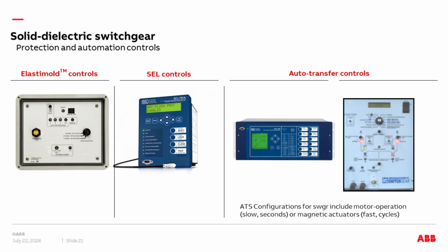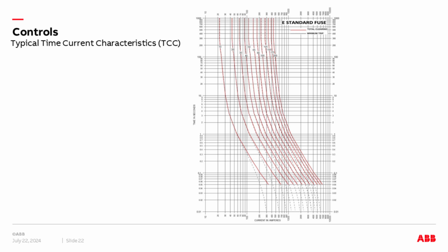Also, in solid-dielectric switchgear, you need controls to, like we talked about, programming interrupters for curves. This type of switchgear works with our own Elastimold brand of controls, but also interfaces with other industry standard controls. I'm showing some Schweitzer control relays here. There's a 751 or 751A. It's quite common for controlling one of the ways, and this one on the right under auto transfer is, I think, the 451. And then the equivalent Elastimold product faceplate shown on the right. So there's quite a range of control options. And the fuse curve I talked about, here's an E standard fuse, you can select this in the control, but you can also manipulate these curve shapes to some degree.